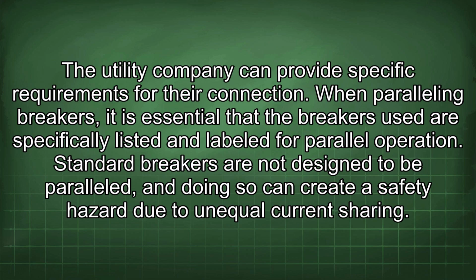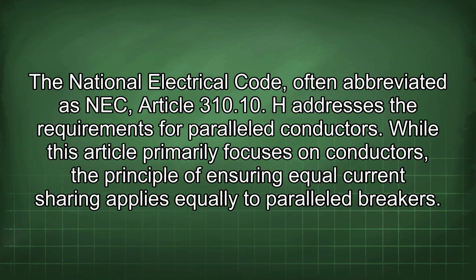When paralleling breakers, it is essential that the breakers used are specifically listed and labeled for parallel operation. Standard breakers are not designed to be paralleled, and doing so can create a safety hazard due to unequal current sharing. The National Electrical Code, often abbreviated as NEC, Article 310.10(H) addresses the requirements for paralleled conductors. While this article primarily focuses on conductors, the principle of ensuring equal current sharing applies equally to parallel breakers.